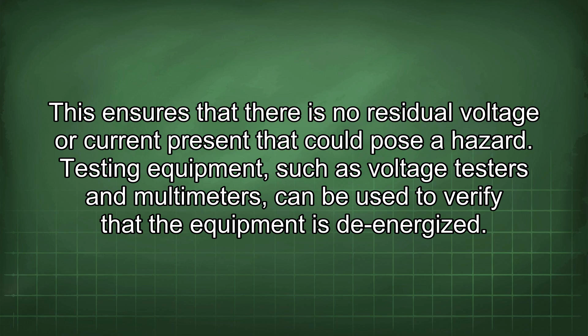Now let's talk about testing. Before starting any electrical work, it is essential to verify that the equipment is de-energized using appropriate testing equipment. This ensures that there is no residual voltage or current present that could pose a hazard. Testing equipment such as voltage testers and multimeters can be used to verify that the equipment is de-energized. It is important to use the testing equipment according to the manufacturer's instructions and to ensure that it is in good working condition.